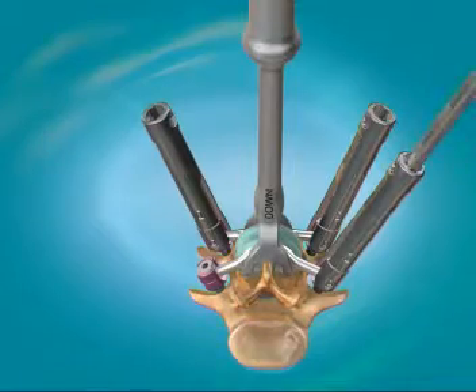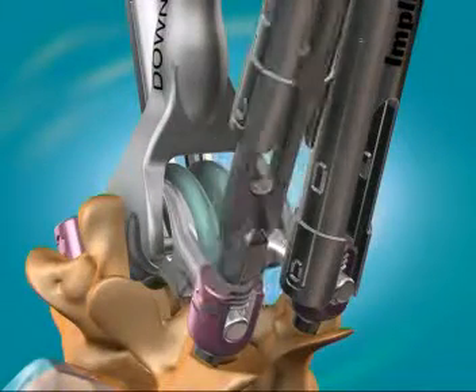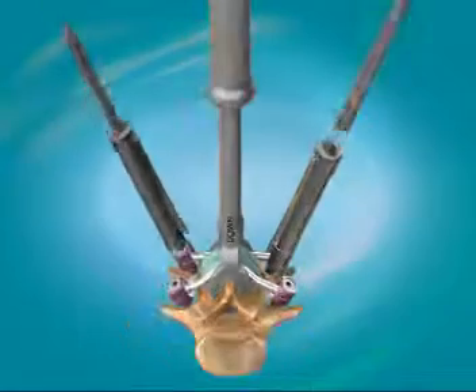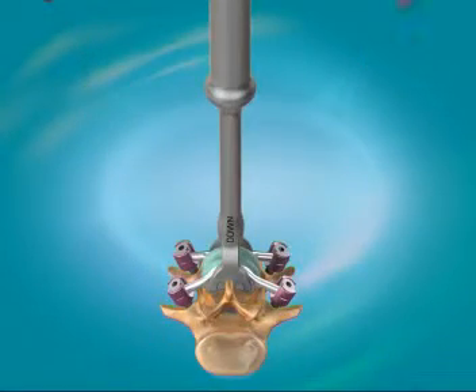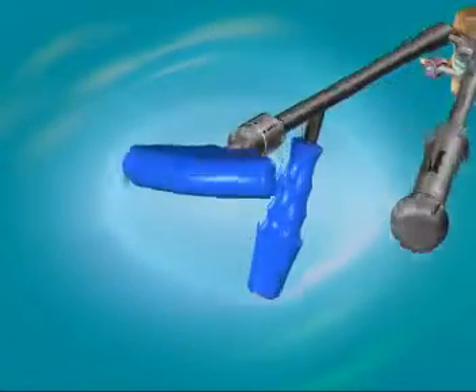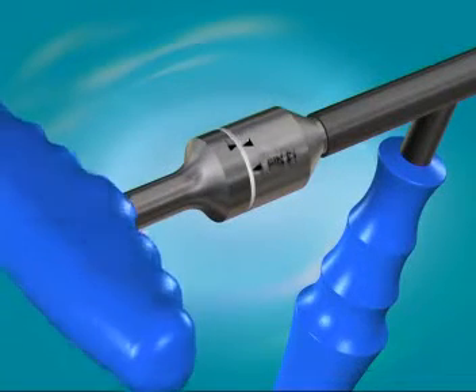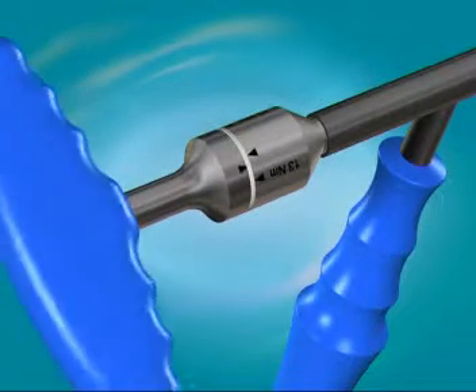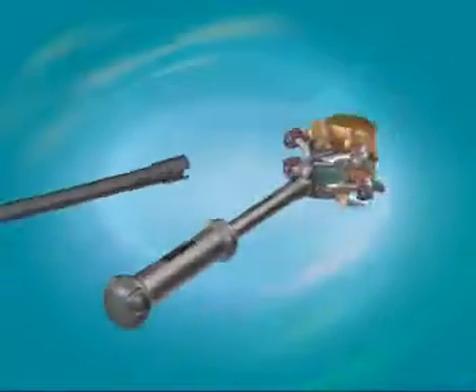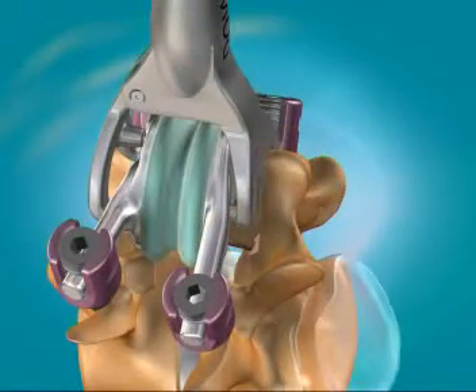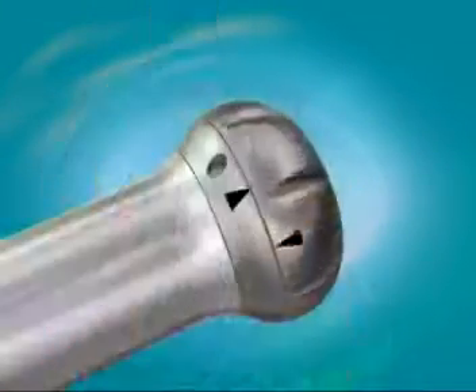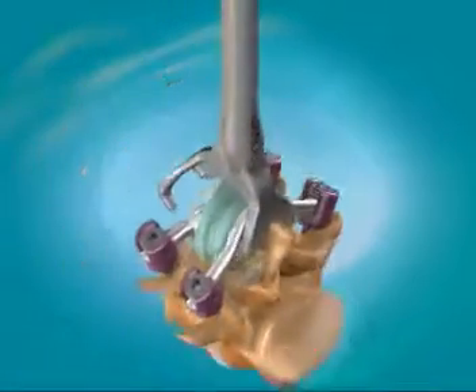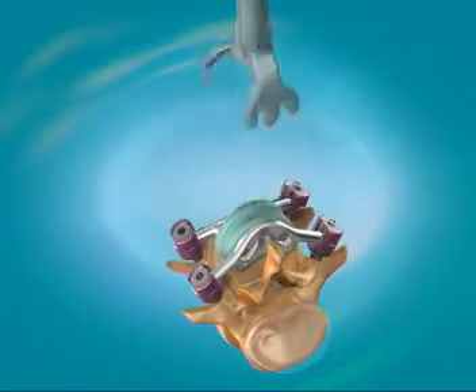Remove the 4 screw guides by inserting the screw finder before proceeding to the next step. Tighten the 4 set screws to 13 Newton meters using the torque wrench and the counter wrench. Remove the holder from the TOPS by turning the knob counterclockwise to open the tongs. Verify final positioning with an X-ray.